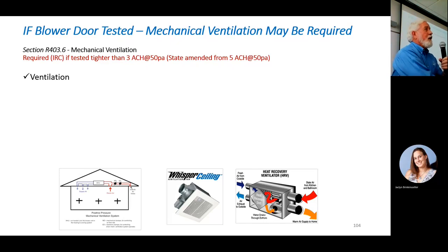And the code says, and ASHRAE, the standards for ventilation and everything, the engineering standards say we need to ventilate continuously, which means the fan runs all the time, or we can do it intermittently and spread it out as much as 1 hour every 4 hours. So if I need 50 CFM of ventilation air continuous, but I don't want to do it continuous, I only want to do it 1 hour every 4 hours, what am I going to need to do? We're going to have to do 200 CFM so that our average over that 4 hour period is 50 CFM per hour. So if we want to just do 1/4 of the time, then we have to do 4 times the rate.